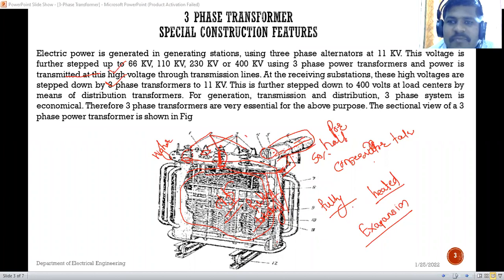फुटेल फुगा. That means it will break. Right? So similarly, if this tank is not provided with a conservator, and if this tank is fully filled and due to overheating the oil expands, then when it expands, the iron body of the transformer may get damaged or it may burst. Iron body काय will damage.